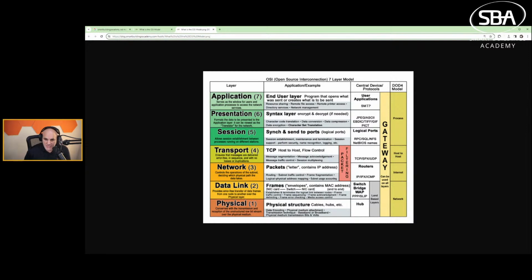Since we want BACnet to be a light protocol, it's UDP. And UDP means connectionless. So TCP is connection oriented, meaning there's that connection between the two networking devices. And if messages are sent, we make sure that they're received and acknowledged. When we have UDP, user datagram protocol, UDP is actually a connectionless protocol, meaning that it's fire and forget messages. And you may be like, okay, but how does that work?